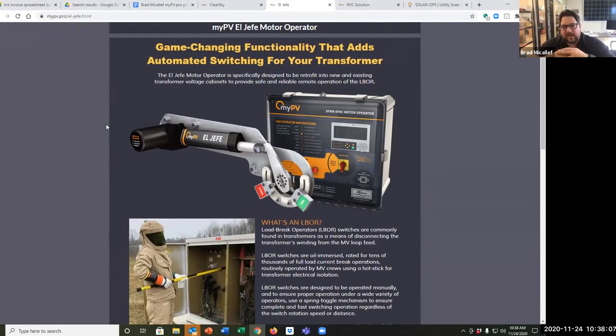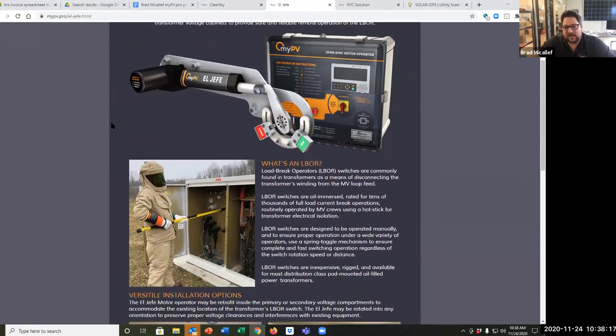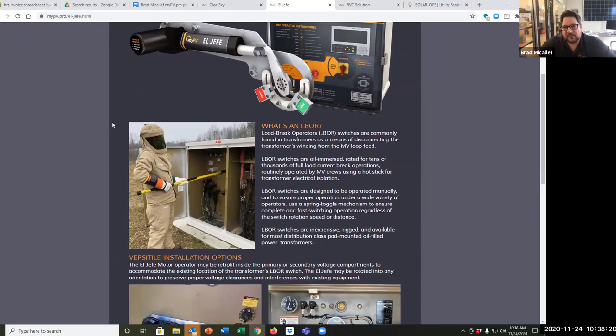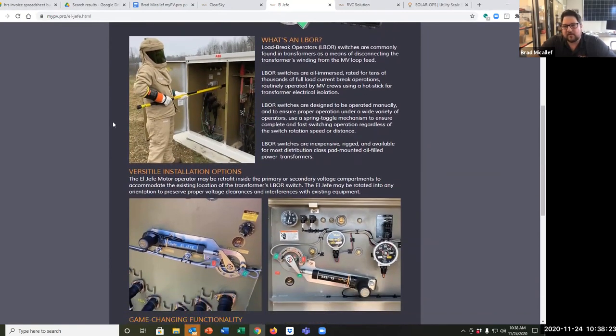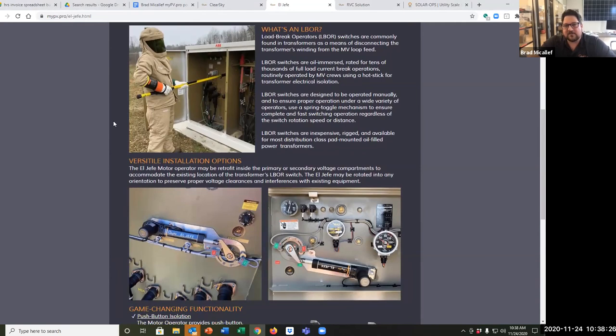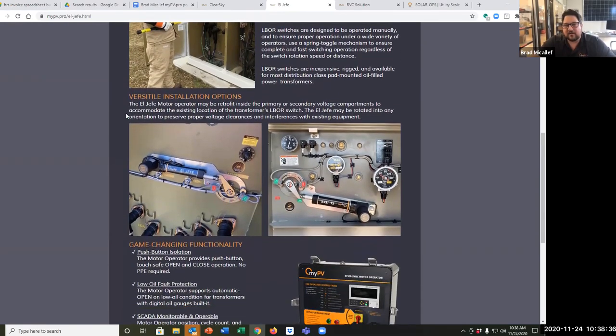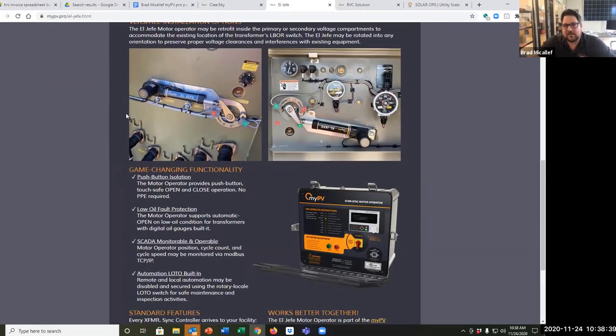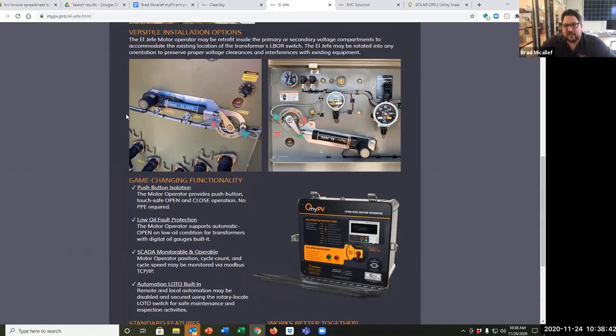As we see solar and now storage penetrate into different markets, different utilities really have challenges with how their grid was built out. As you're adding all of these step-up transformers into fairly rural areas that were not designed to handle large variations in voltage sag, or to have a generator at the tail end of a low voltage distribution feeder, when you start adding these solar projects and step-up transformers, you start running into problems with what's called inrush current when these transformers turn on.